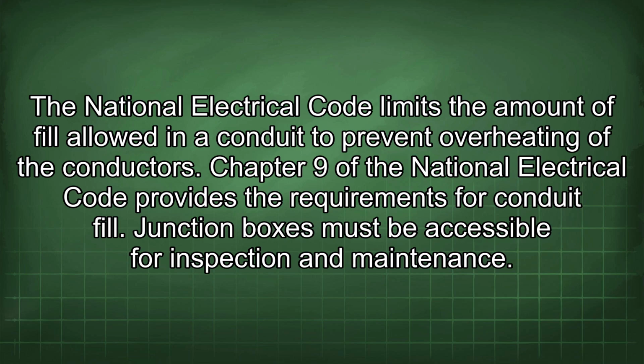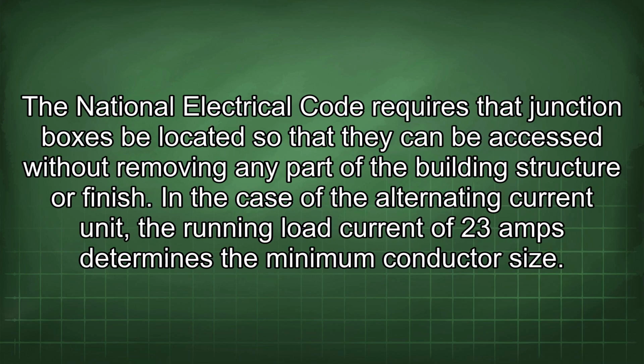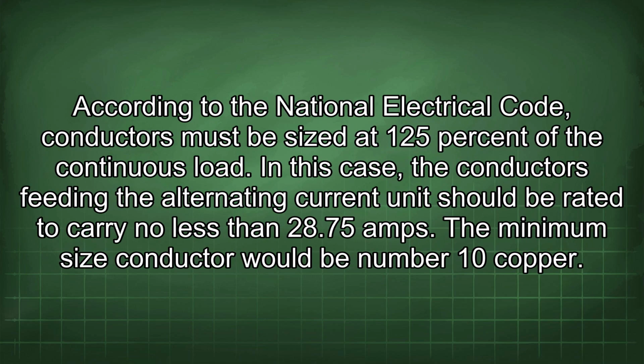Junction boxes must be accessible for inspection and maintenance. The National Electrical Code requires that junction boxes be located so that they can be accessed without removing any part of the building structure or finish. In the case of the alternating current unit, the running load current of 23 amps determines the minimum conductor size. According to the National Electrical Code, conductors must be sized at 125% of the continuous load. In this case, the conductors feeding the alternating current unit should be rated to carry no less than 28.75 amps. The minimum size conductor would be number 10 copper.